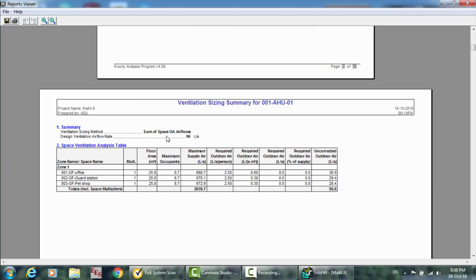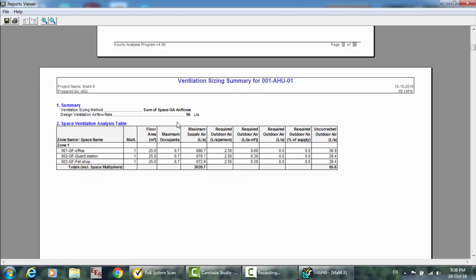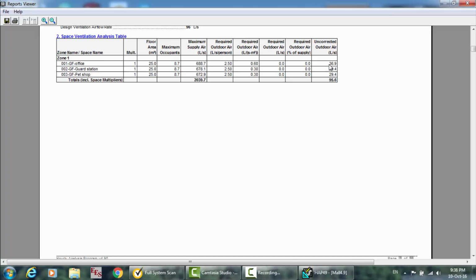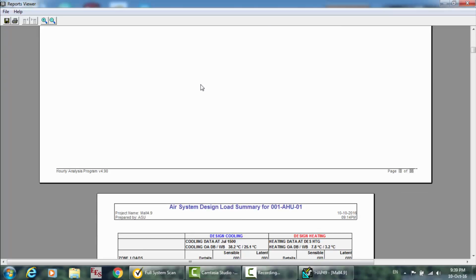Then here the summary ventilation sizing method, sum of space OA airflows. Okay, and here the space ventilation analysis table, floor area, maximum occupants, and maximum supply air, the required outdoor air for each space, required outdoor air liter per second per square meter. It is kind of multiplying the number by number of persons and the floor area. And here the uncorrected outdoor air and required outdoor air percentage of supply. And here is the total. This is for this space 1, space 2, space 3. And here the total of maximum supply air. This allows you to select the appropriate machine.